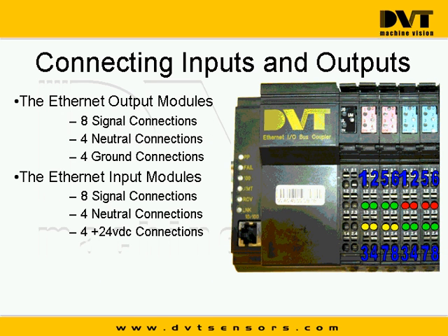Now, how do you connect your inputs and your outputs? Well, first of all, we need to understand where they're located, how they're labeled, and what we need to connect to them. While this is filling in, I want to point out that each one of these modules, let me highlight a couple of these for you, the output modules you're seeing in pink here, with a nice big X on top of them, carry 4 outputs each. So if I have these 2 modules right here that you're looking at, technically I have 8 total outputs. And that's exactly what you're seeing labeled here in blue.